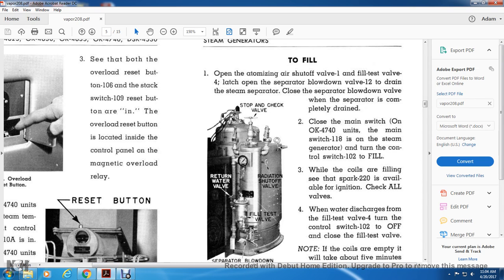To fill, open the atomizing air shutoff valve 1 and the fill test valve 4. Open the separator blowdown valve 12 and drain the steam separator. Close the separator blowdown valve when the separator is completely drained. Close the main switch on the OK4740 unit. Close the main switch 118 on the steam generator, and turn the control switch 102 to fill. While the coils are filling, see that the spark 220 is available for the ignition.